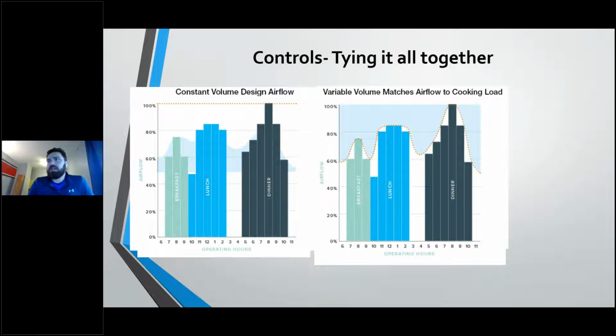The final thing that I would mention here is twofold, what we're seeing in the market and some design considerations. Prices between the two different types of units across the board have really come together. And historically, if you were going to do, say, an elementary school or a middle school, you would say, okay, well, I know that I'm not doing a ton of cooking under there. It's still a type 1 system, and I'm not doing a ton of cooking. So what an engineer or someone would do is they would design this with a constant volume system. Let's just say 3,000 CFM, assuming full load is 100% of 3,000. The idea being it was a lower upfront cost, so we're going to do a constant volume design.